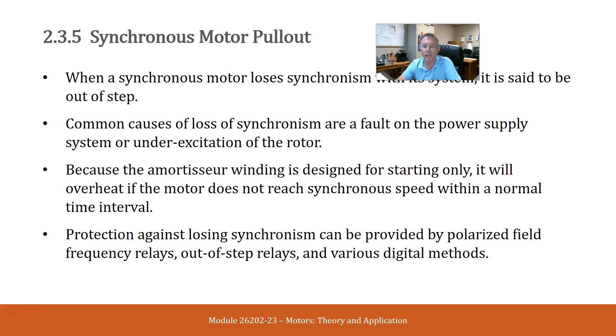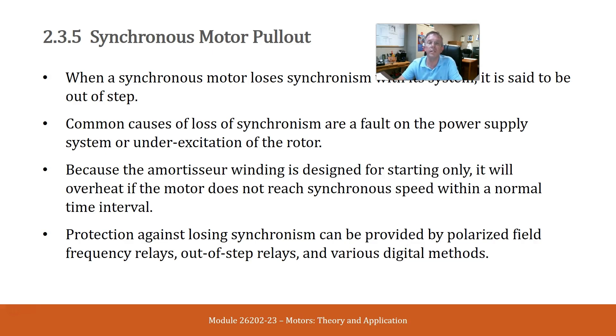Because the amortisseur winding is designed for starting only, it will overheat if the motor does not reach synchronous speed within its normal time interval. Protection against losing synchronism can be provided by polarized field frequency relays, out-of-step relays, and various digital methods.